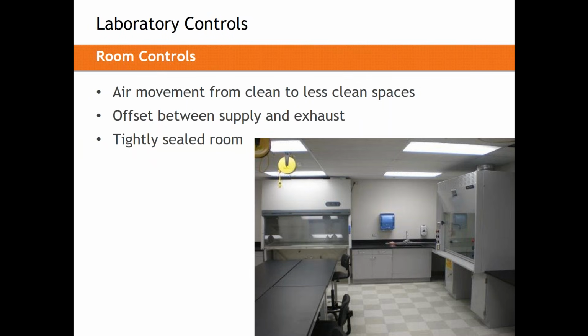Generally speaking, we want air to move from a clean space to a less clean space. To ensure that happens in a certain direction, we are always going to use some sort of offset between all of your supply and all of your exhaust. Now, our goal as design engineers is not to create a system with a certain amount of leakage, with a certain amount of offset to hit a certain pressure. Our job is not to line up all three of those things. Our job as mechanical designers is to ensure we create a mechanical system that is capable of achieving a certain pressurization given a range of leakage rates in my space. Basically giving my balancing and commissioning teams the authority and ability to correctly pressurize these spaces. That is our job as designers.